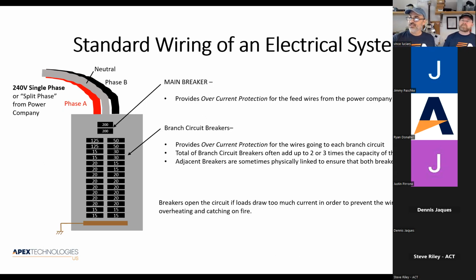But what is the purpose of this breaker panel? Circuit breakers are there to protect the wire. If you put too much current through a wire, the wire will get hot, and the longer that current flows through it, the heat builds up and the wire could catch on fire. So that's why you have circuit breakers. The main breaker you can see there is really to protect the supply wires coming in. The individual circuit breakers are there to protect the wires that are going out to the branch circuits.